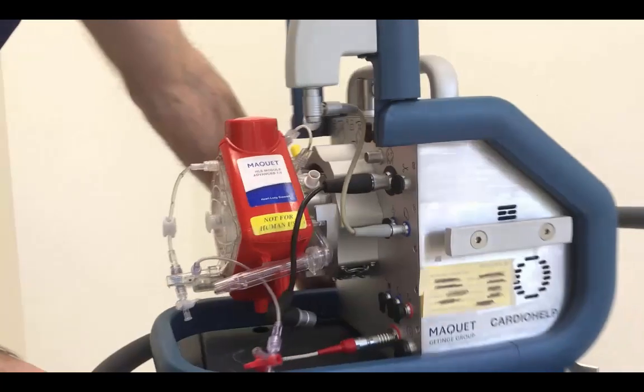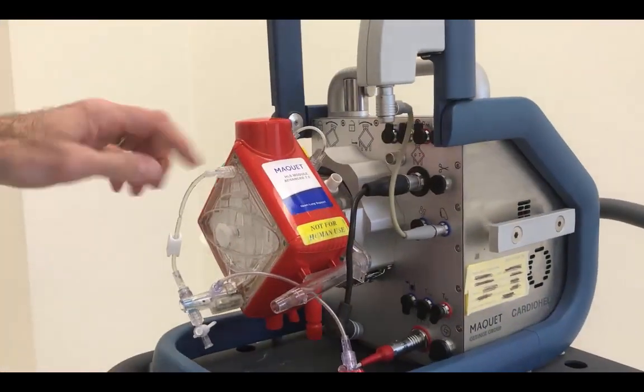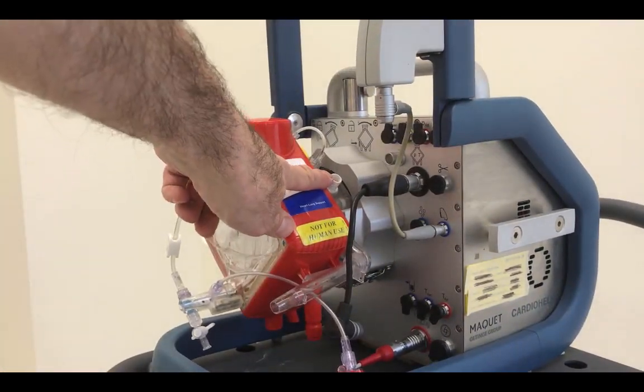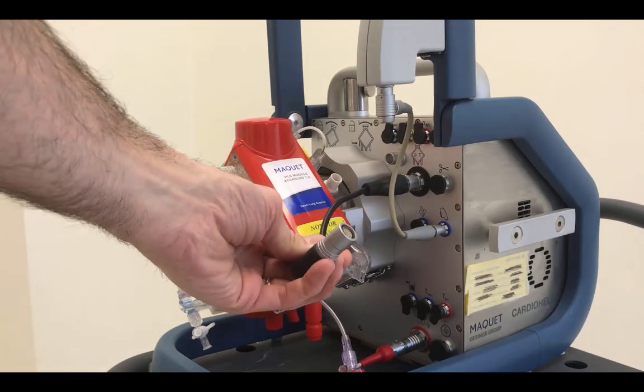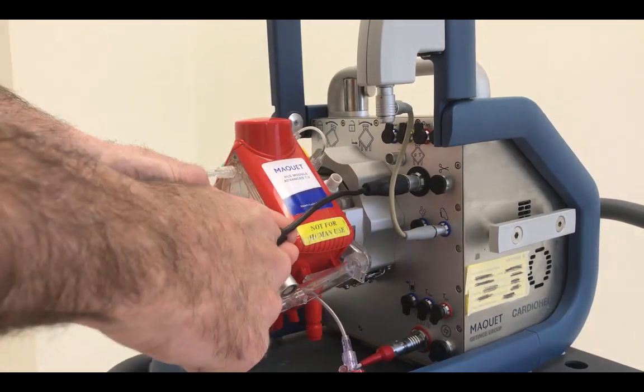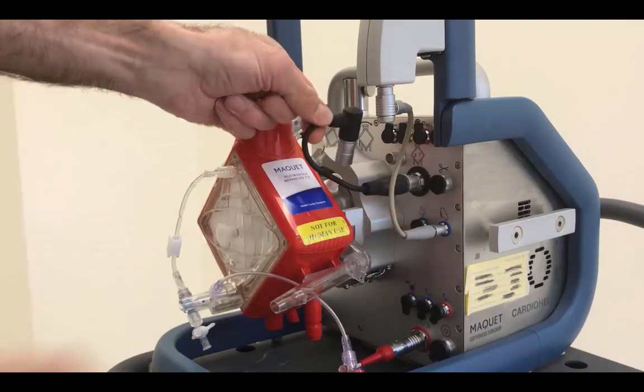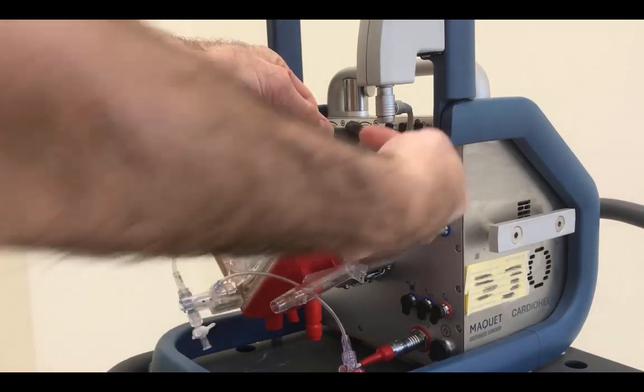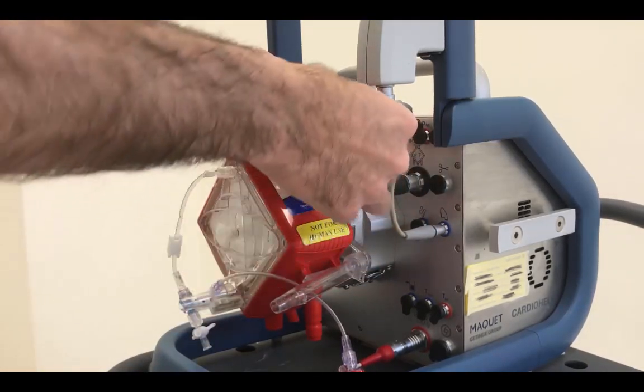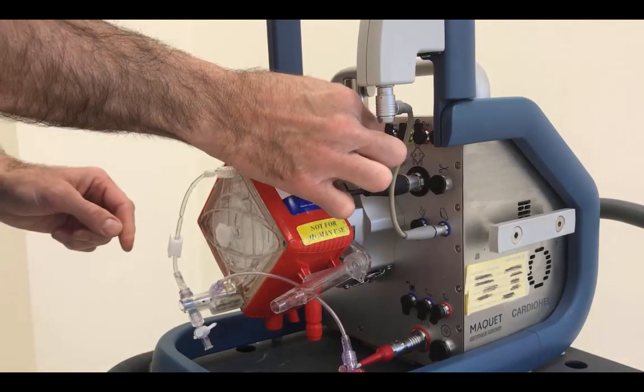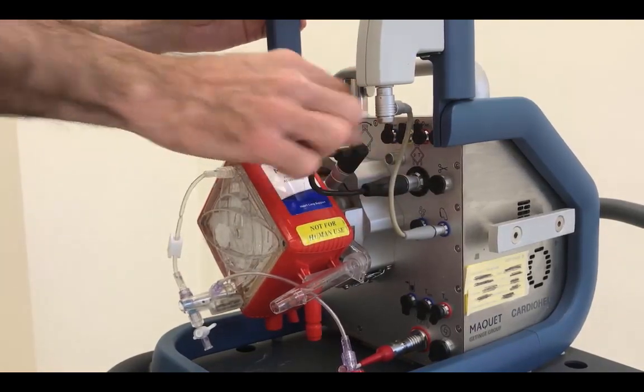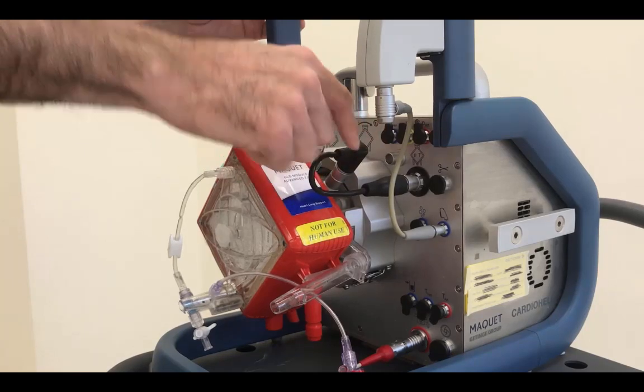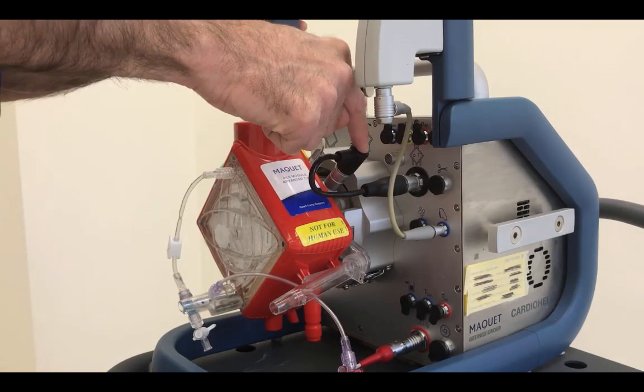There's a port right here for the other end of this cable. This cable has a right angle on it, and the right angle is always oriented this way. The wire comes out and points back out across the oxygenator. This goes in. Just give it a little wiggle, see that it seems like it's fitting well, and then press it in tight.